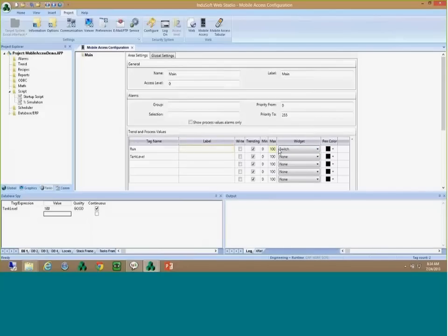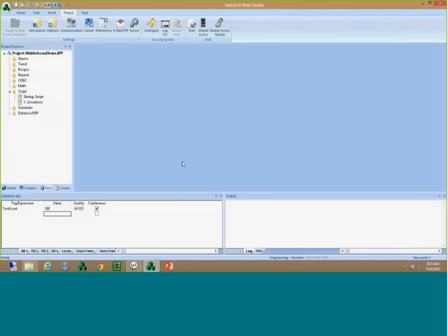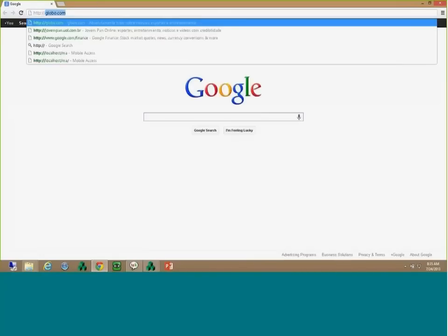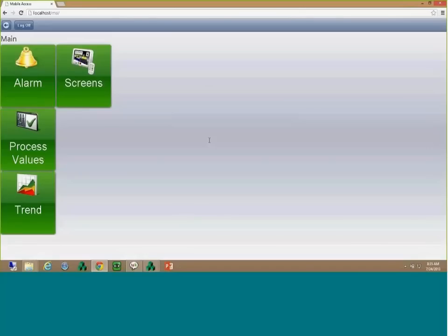You can configure 'run' as a switch — a variable you want to be able to write to. For 'tank level', you can select one of the gauges to display it. Let's add a circular gauge and save this. Once this is saved and running, I can open any of my browsers. Let's start with Chrome. Once I log in, it brings me to the Mobile Access interface. All I did was add two variables — I didn't have to do any fancy configuration, IP addresses, nothing. We handled all that for you.